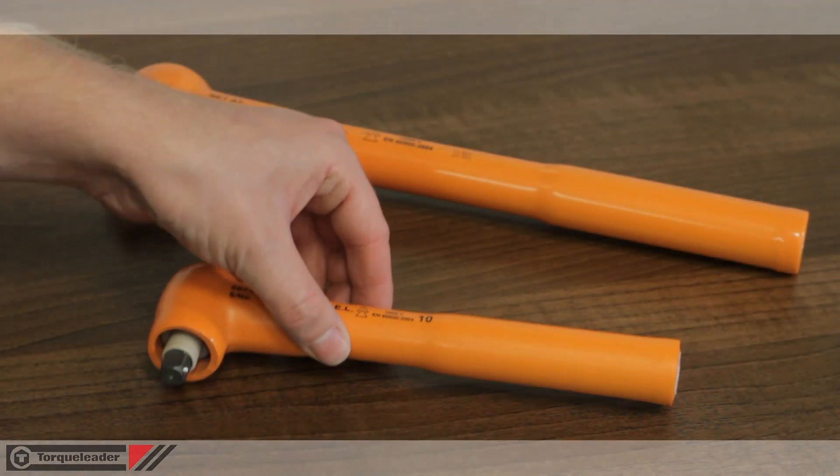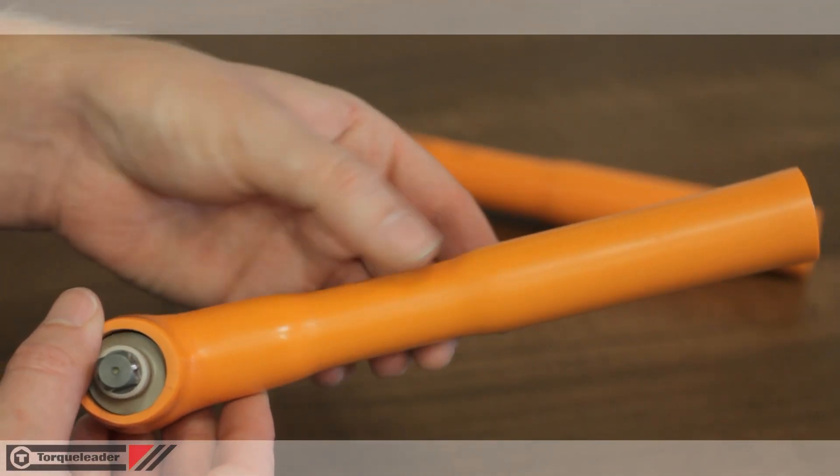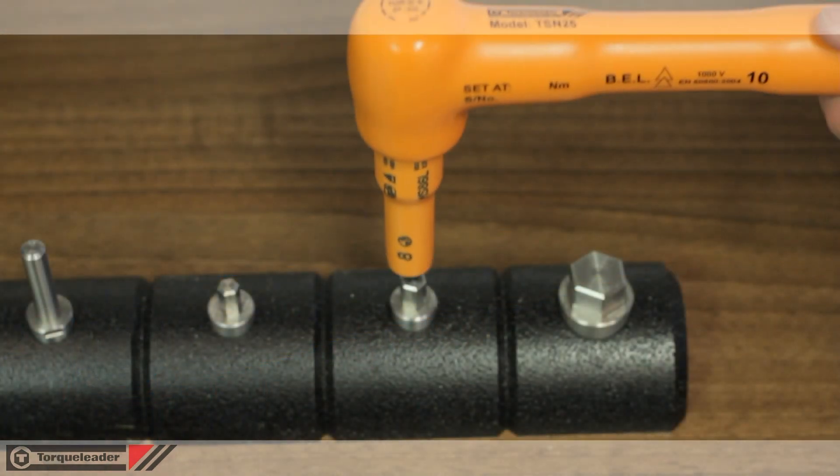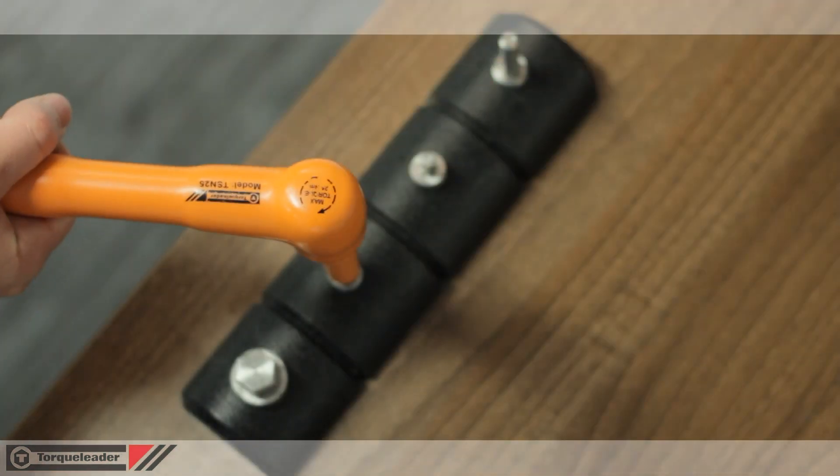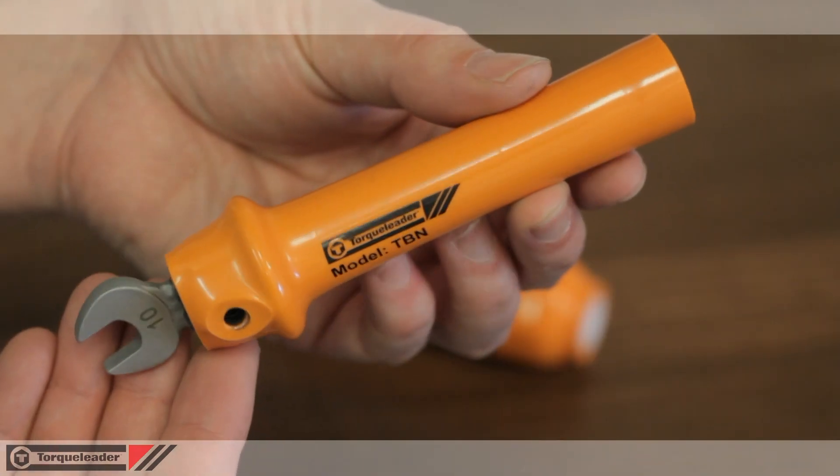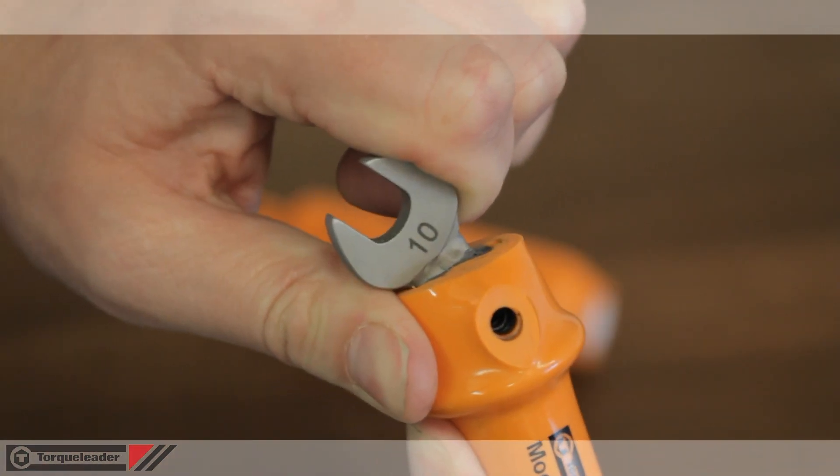Most Torque Leader 1000 volt tools incorporate a slipping mechanism. This prevents the operator from applying more than the set torque. A 20 degree breaking mechanism is used with the open jaw fittings.